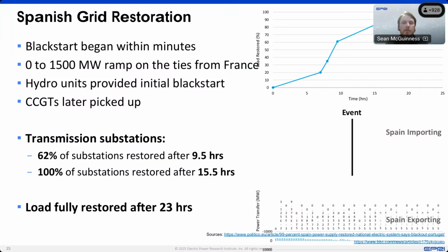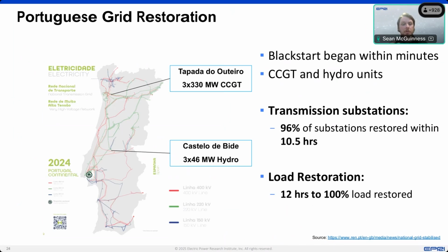In Portugal, they actually have two main black start resources. In the north, they have a combined cycle unit that's 330 megawatt gas turbines and steam turbine sets, and in the middle of Portugal, they have 3 by 46 megawatt hydros. So they were able to bring those into action again, beginning within minutes.